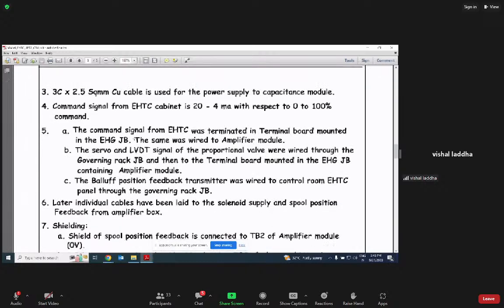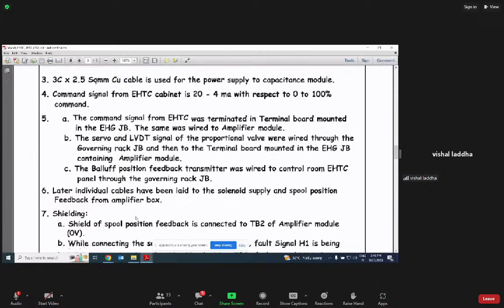And the fifth point is also a very critical point. The command signal from EHTC was terminated in a terminal board mounted in the EHG JB. The same was wired to the amplifier module, the servo and LVDT, and all these should be taken care of because of the shielding. Initially BHL introduced a metallic JB, and through this metallic JB some hunting was observed, so they replaced the metallic JB with a fiber JB, and later individual cables were laid to the solenoid supply and spool position feedback amplifier box.